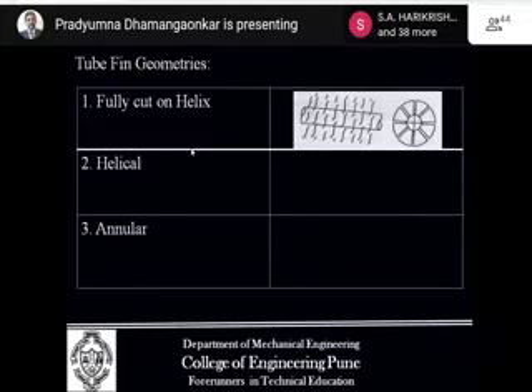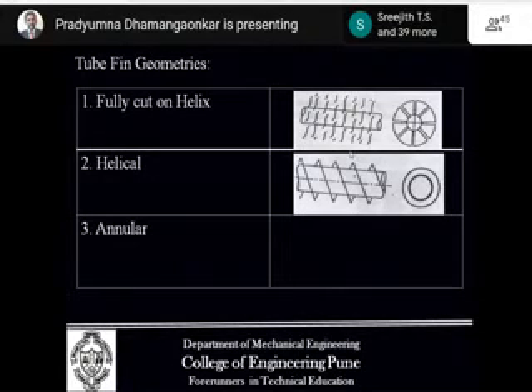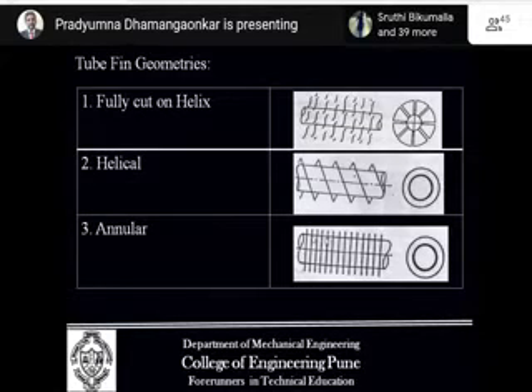Then on the shell side, as we know, it is possible to provide different fins on the outer surface. The importance of providing fins is to increase the surface area, and second, to impart turbulence to the flow. So the researchers have tried different fin geometries. This is fully cut on helix, as shown. The tube is provided with fins which are fully cut, and these tubes are placed in a helical order or helical shape. This is full helix. Fins are spirally fixed. These are the annular fins which are placed on the outer part, and thus the heat surface area is improved.